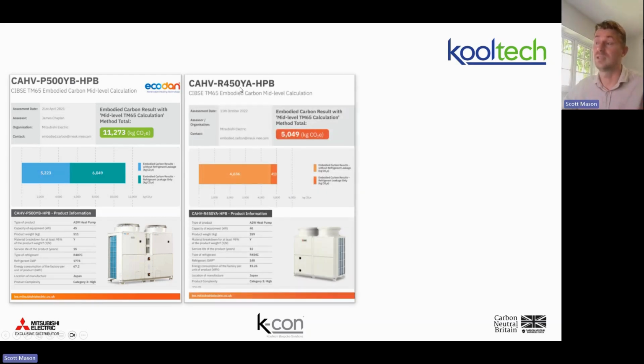The unit that's replaced it, the CAHV-R, which is now our new workhorse that we've been supplying for a very long time now, actually, uses a 454C, but you can see the impact that has. The embodied carbon is less than 50% of its predecessor's embodied carbon, and the reason is almost solely down to the refrigerant, because this teal section is the embodied carbon with refrigerant leakage. The orange darker section here is with refrigerant leakage. So historically, more than 50% of the embodied carbon of my commercial heat pump was in the refrigerant. It's a big number. Now it's less than 10%.